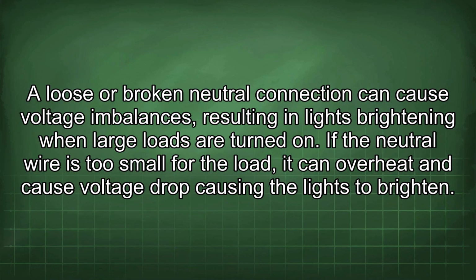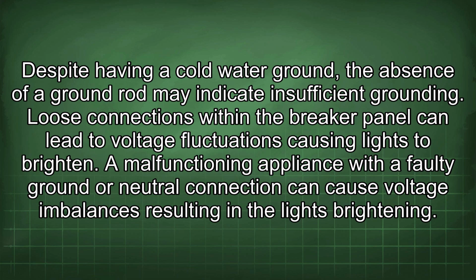A loose or broken neutral connection can cause voltage imbalances, resulting in lights brightening when large loads are turned on. If the neutral wire is too small for the load, it can overheat and cause voltage drop, causing the lights to brighten. Despite having a cold water ground, the absence of a ground rod may indicate insufficient grounding. Loose connections within the breaker panel can lead to voltage fluctuations, causing lights to brighten. A malfunctioning appliance with a faulty ground or neutral connection can cause voltage imbalances, resulting in the lights brightening.